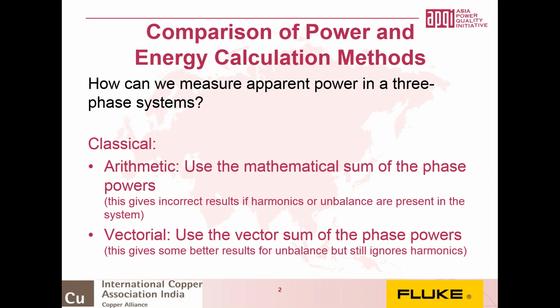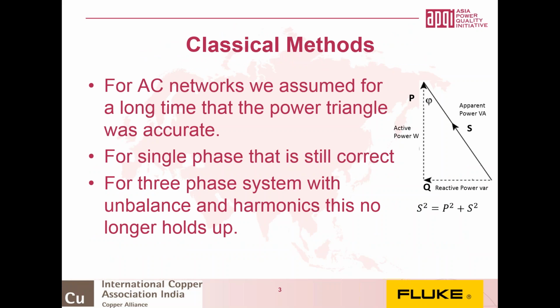But if there is unbalance and harmonics present in the system, this can produce some results which are not necessarily correct. The second method, of course, is to do the same summation but vectorially. The reason we do it vectorially is that we're looking at the power triangle. For AC networks, we've assumed for a long time that this was accurate. For single-phase systems, that's still fine. But when unbalance is present, there are some potential errors. In this case, the square of the apparent power is the sum of the power squared plus the reactive power squared, which I guess we all know for a long time.